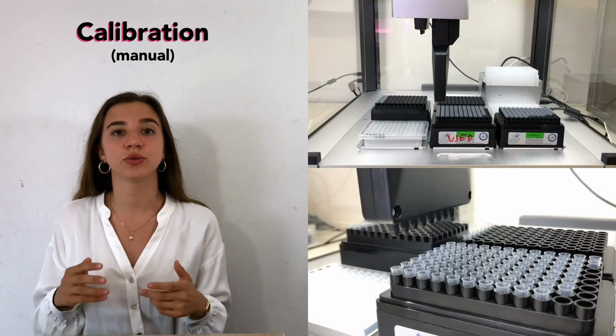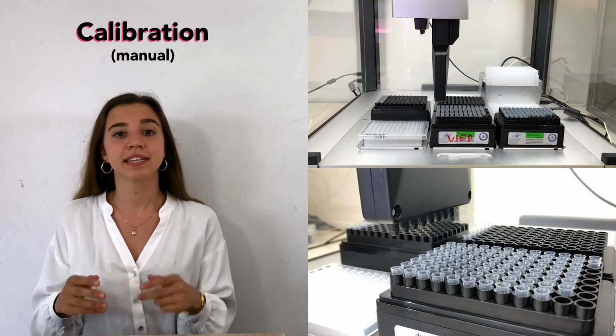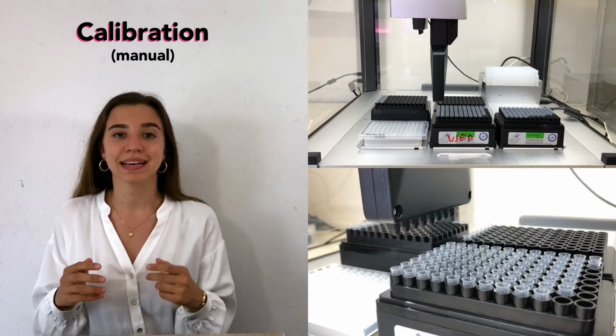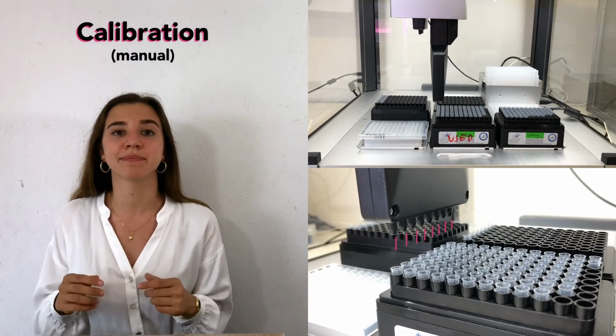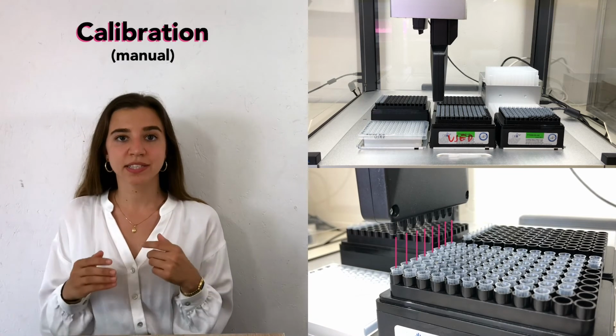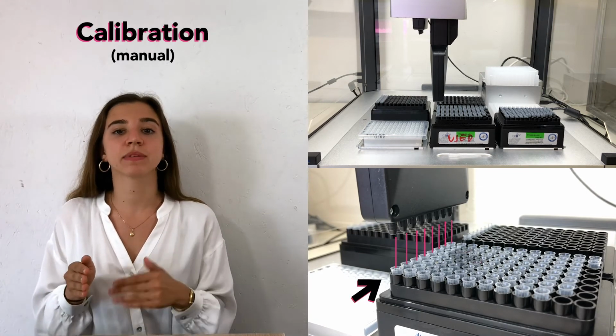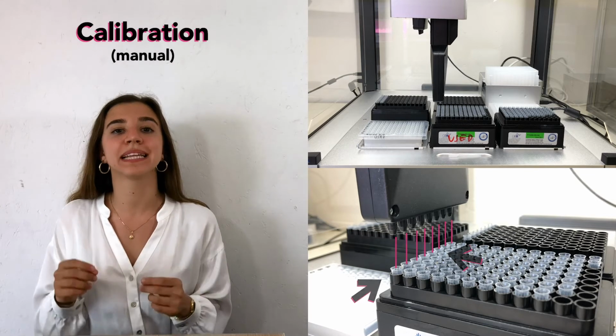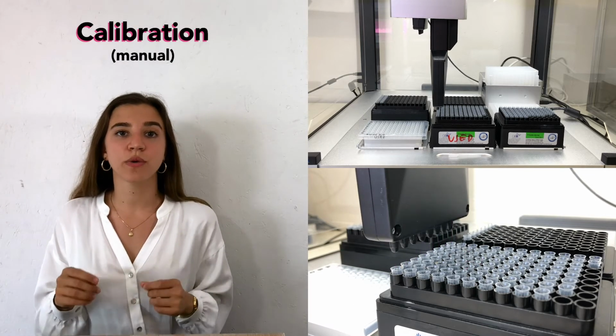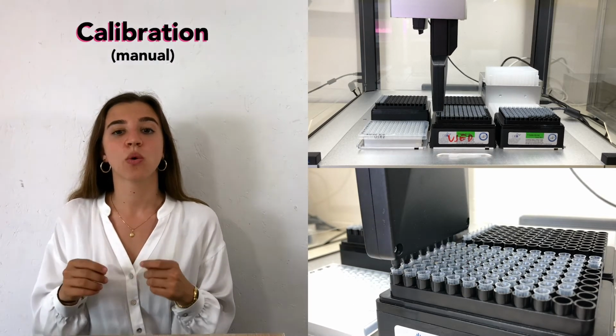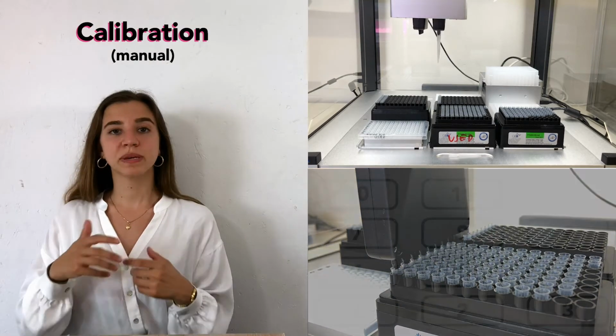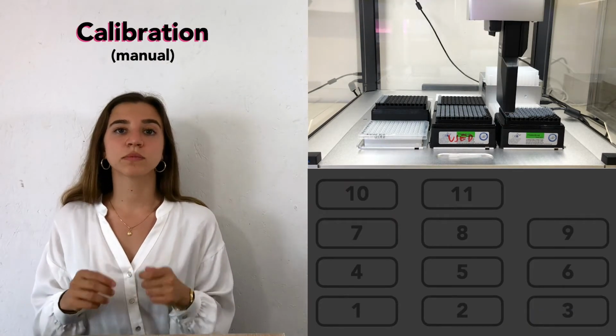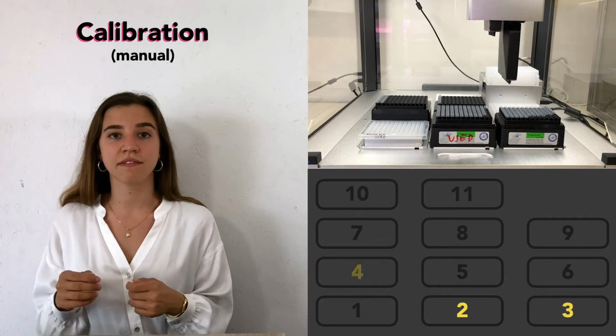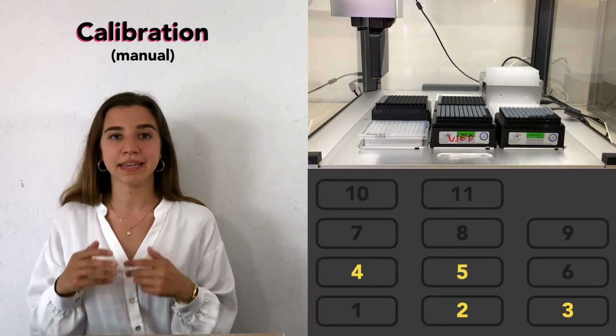First, the OT-2 will calibrate the tip racks. It is critical that you move the pipette until it is centered above the tips in the first column. You must check head on and from the side to ensure that it is completely centered. Then lower the pipette until it is flush with the top of the tips. This will be done sequentially, starting from slot 2 until slot 5 for the first column in each tip rack.